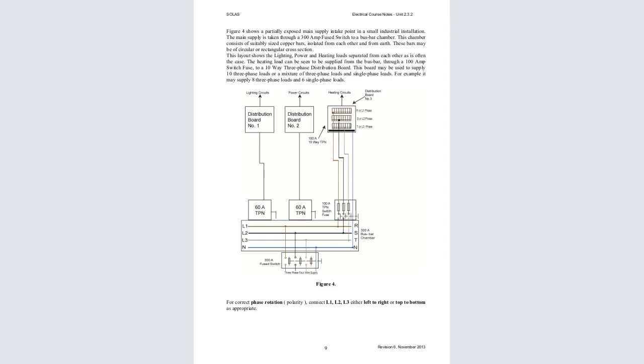Now, figure 4 shows a main supply intake point in a small industrial installation. The main supply is taken through a 300 ampere fused switch to a bus bar chamber. This chamber consists of suitably sized copper bars isolated from each other and from earth.